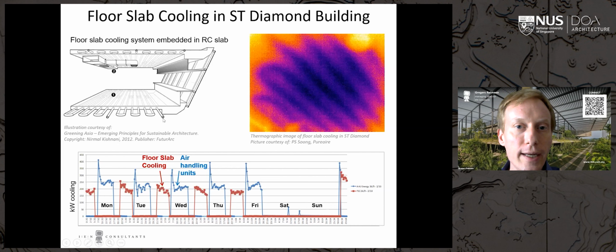So that means throughout the night, we are running water of 18 degrees through these slabs. And we are basically cooling the concrete slab down, the floor and the ceiling throughout the night. So come 6 in the morning or so, we switch off the system. And then this cooling is slowly released to the space passively during the office hours. So if we had not had this floor slab cooling system, then the normal aircon cooling load would have been about 40% higher. So the advantage here is that we can shift, in this case, about 40% of the cooling to the nighttime, where you typically have cheaper energy rates. And we can also help to reduce the maximum demand of the cooling because we have a lower maximum consumption because it's spread over the 24 hours.